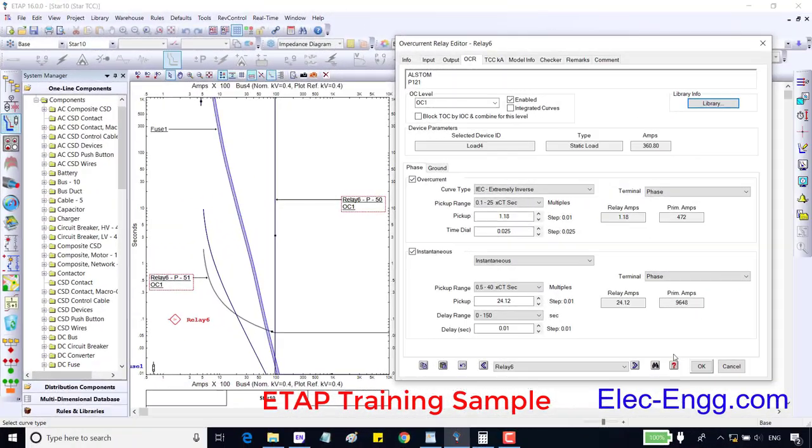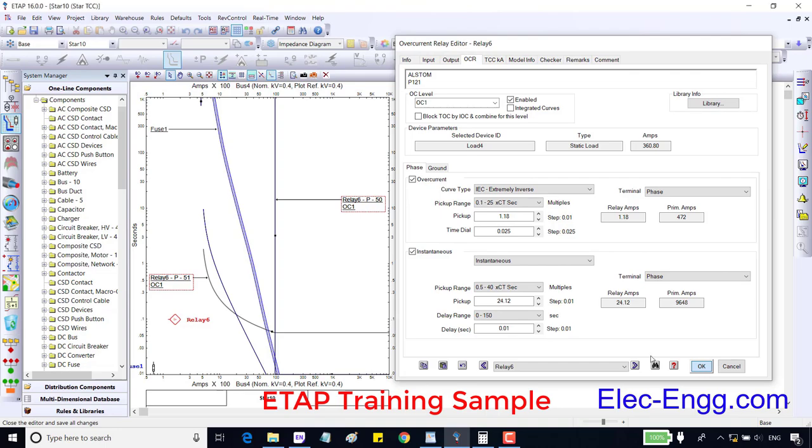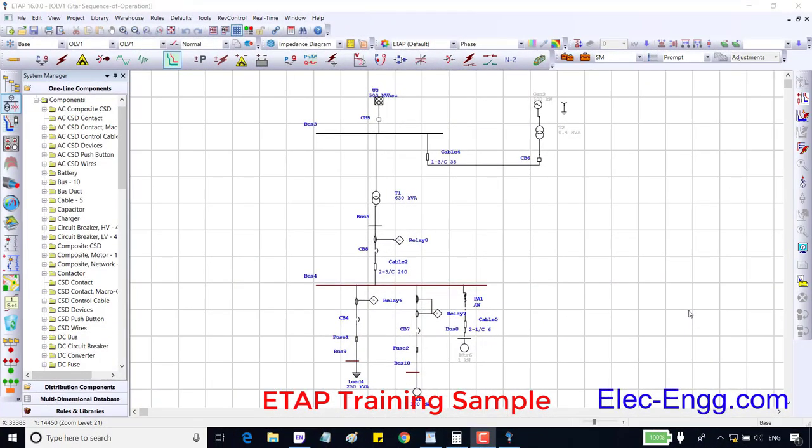If you want to coordinate the relay with the fuse, it is better to use extremely inverse. In the previous session we have seen how to add fuse, overcurrent phase and ground elements. In this session we are going to overview the protection type in each element.